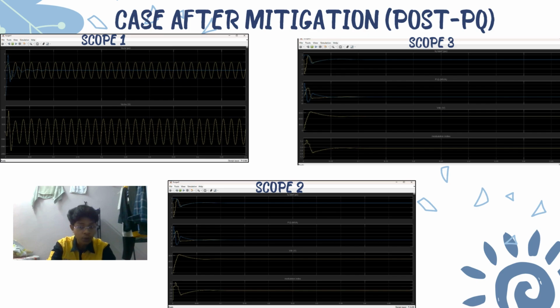In scope 2, as we can see, the reactive current Iq closely tracks its reference, Iq ref. The modulation index stays within a safe range of 0 to 1.33 per unit. It varies smoothly, showing stable operation and effective switching between the capacitive and inductive modes. The reactive power Q is adjusted up to plus and minus 2.7 MVA, showing a fast response within one cycle, and the DC voltage remains stable.